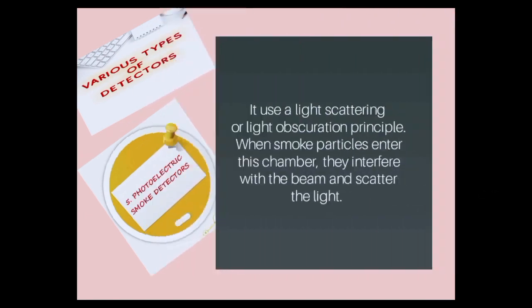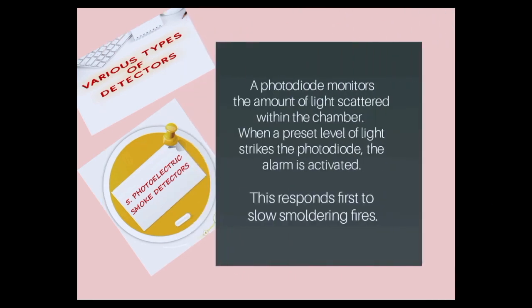The fifth type is the photoelectric smoke detectors. It uses a light scattering or light obscuration principle. When smoke particles enter this chamber, they interfere with the beam and scatter the light. A photodiode monitors the amount of light scattered within the chamber. When a preset level of light strikes the photodiode, the alarm is activated. This responds first to slow smoldering fires.